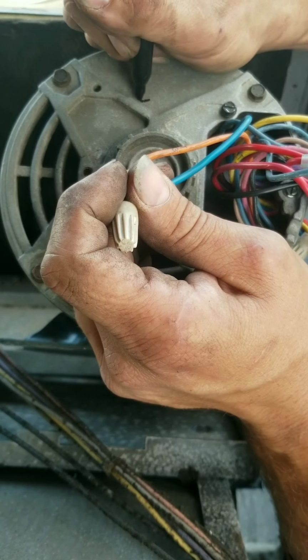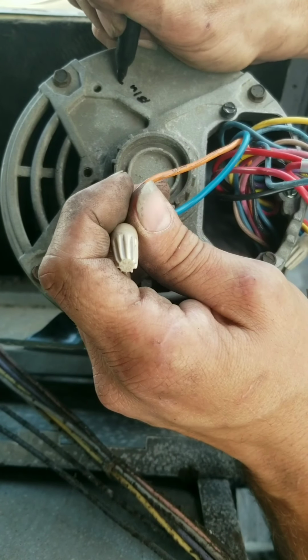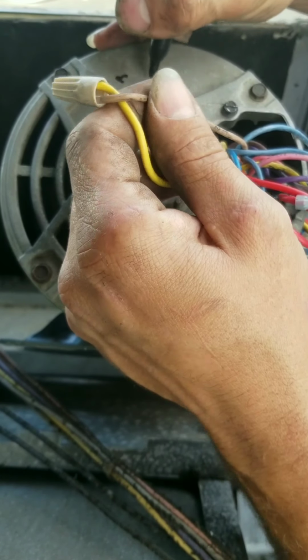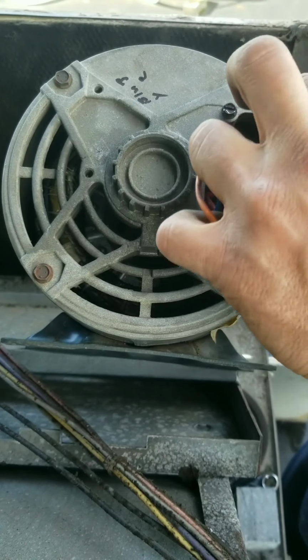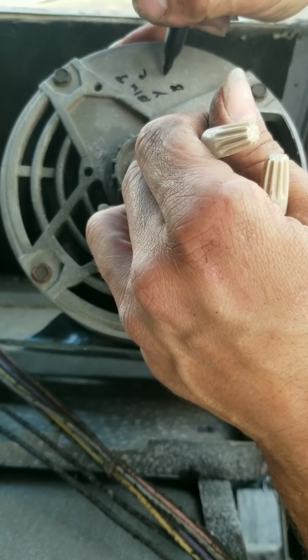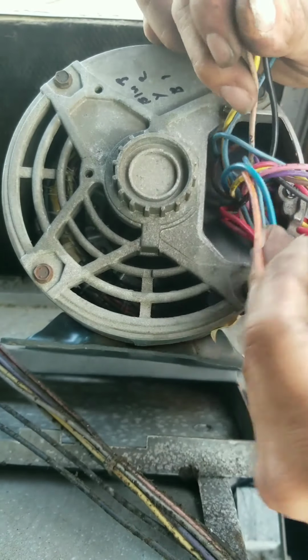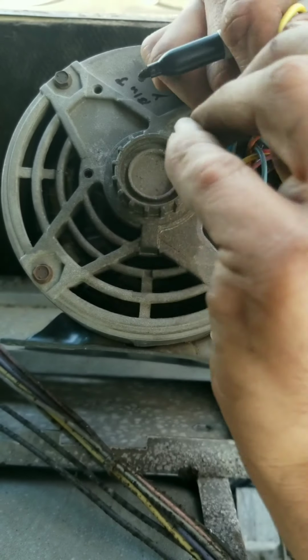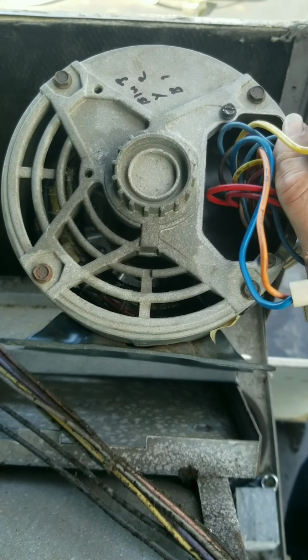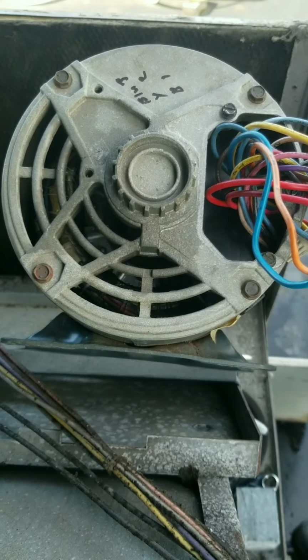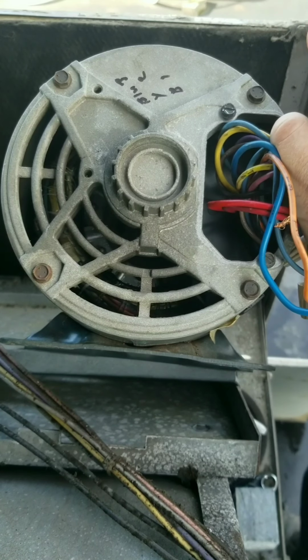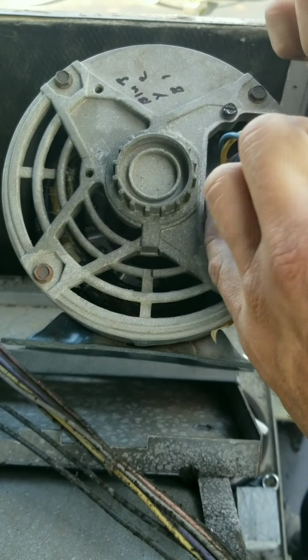So we're going to verify our line 1, 2, and 3. Blue's line 3. Yellow's line 2. Black's going to be line 1. That way we get our rotation correct. We're wired for 460 volts, so we'll get our new motor popped in here and see what happens.